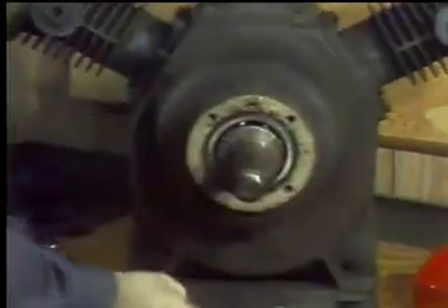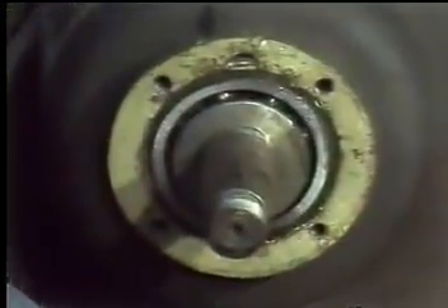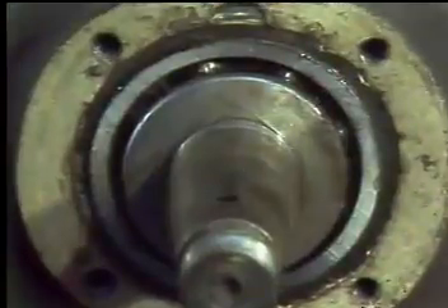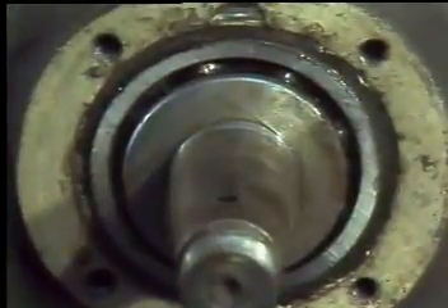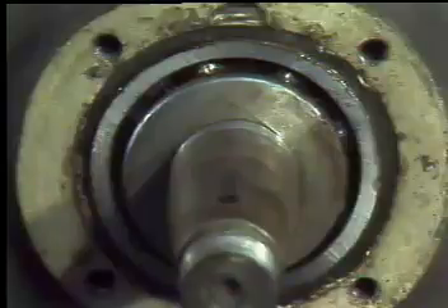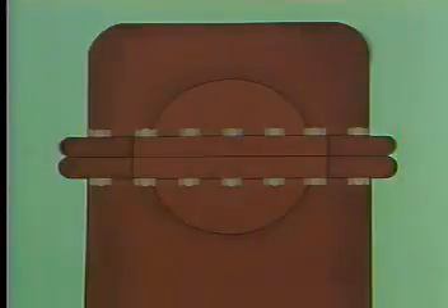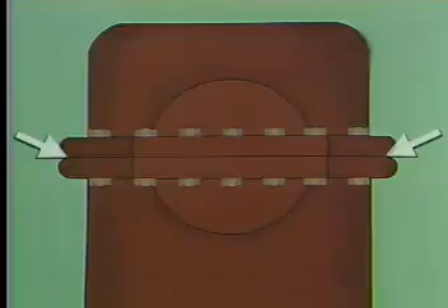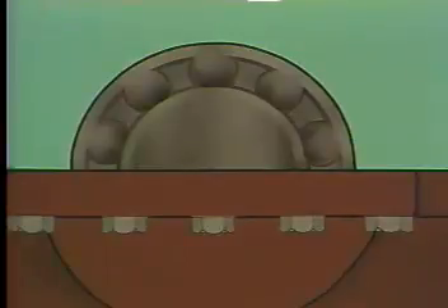The solid types of built-in housings usually have removable end caps. Removing the end caps allows the bearing and the shaft to be taken out of the machine so that the bearing can be worked on. With a split-type built-in housing, there is a joint in the machine's casing that must be taken apart to get to the bearing.